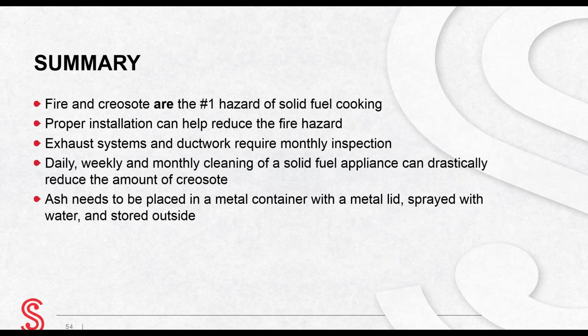Let's recap. The main hazards of solid fuel cooking are fire and creosote. Proper installation of solid fuel appliances can help reduce the fire hazard. Exhaust systems and ductwork covering the solid fuel cooking appliance require monthly inspection and cleaning if necessary. To reduce the amount of creosote in a solid fuel appliance, daily, weekly, and monthly cleaning is necessary. Ash needs to be placed in a metal container with a metal lid, sprayed with water, and stored outside.